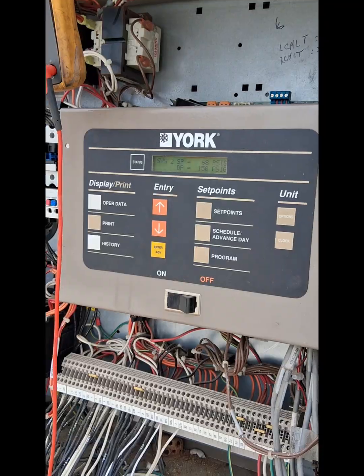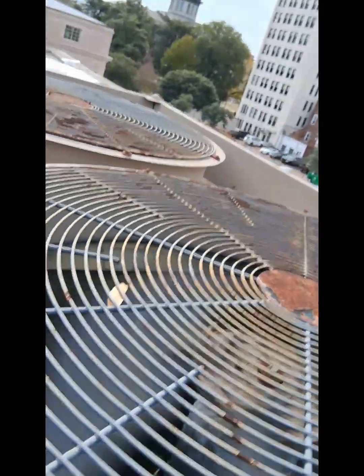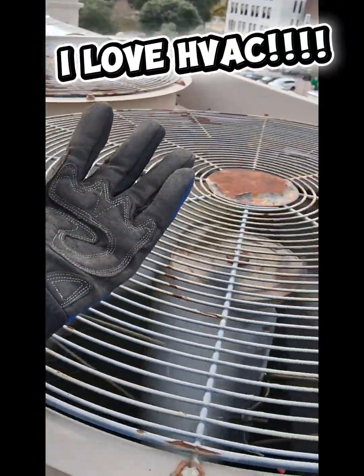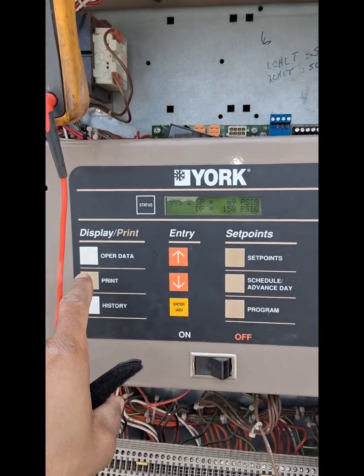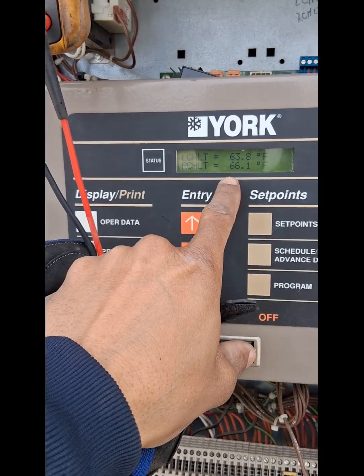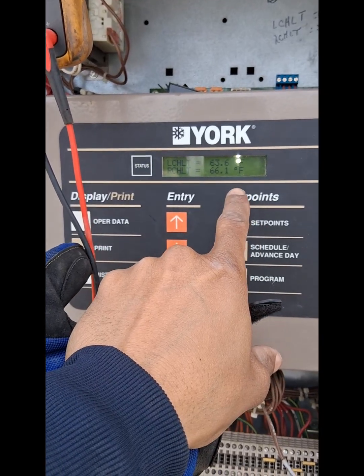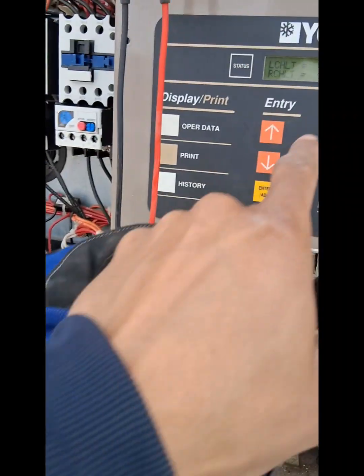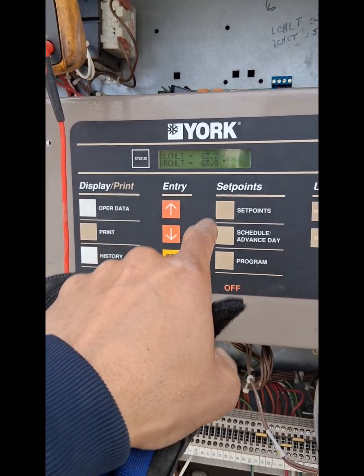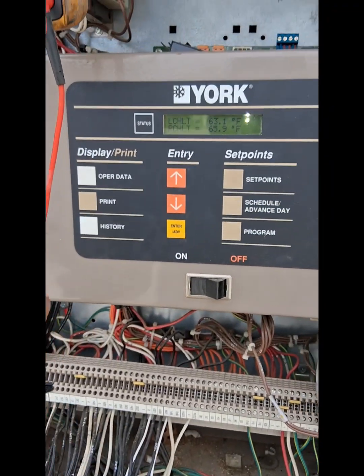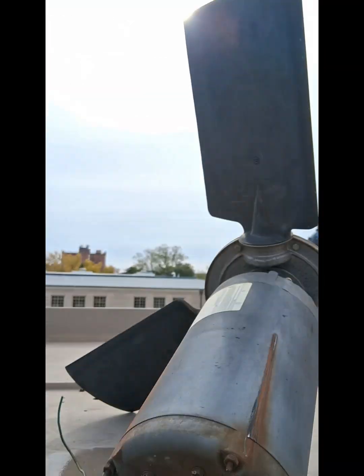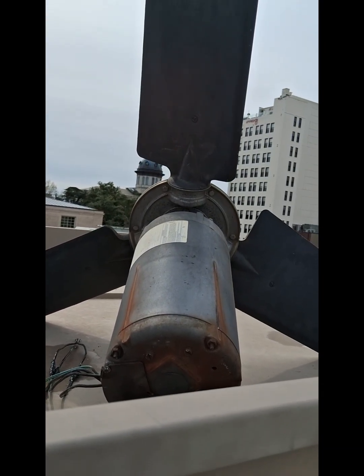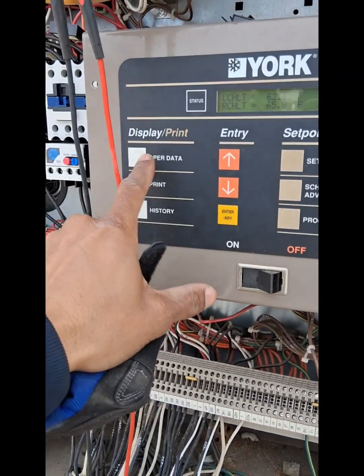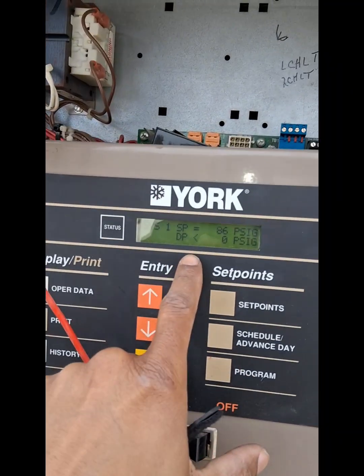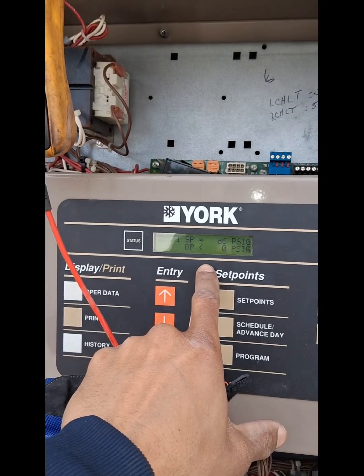We are back up and running. I changed the fan. That's at 63.8. See how low it'll get. They got 2 compressors on this stage, so that'll drop down. But second compressor just kicked in, so I'm gonna just watch it lower. And I took the fan motor off of circuit 1 because it's already bad. There's no point for me to put it back in. I'm gonna drop it down. So I gotta quote a discharge pressure transducer for circuit 1 and a new fan motor.